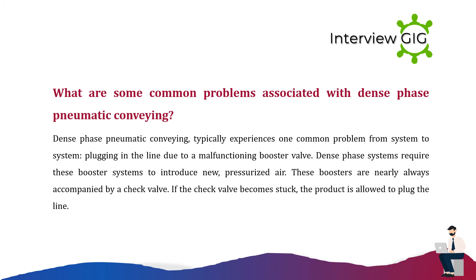What are some common problems associated with dense phase pneumatic conveying? Dense phase pneumatic conveying typically experiences one common problem: plugging in the line due to a malfunctioning booster valve. Dense phase systems require booster systems to introduce new pressurized air. These boosters are nearly always accompanied by a check valve. If the check valve becomes stuck, the product is allowed to plug the line.